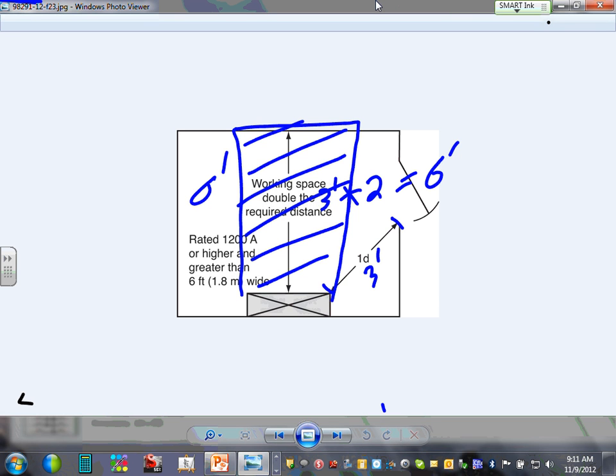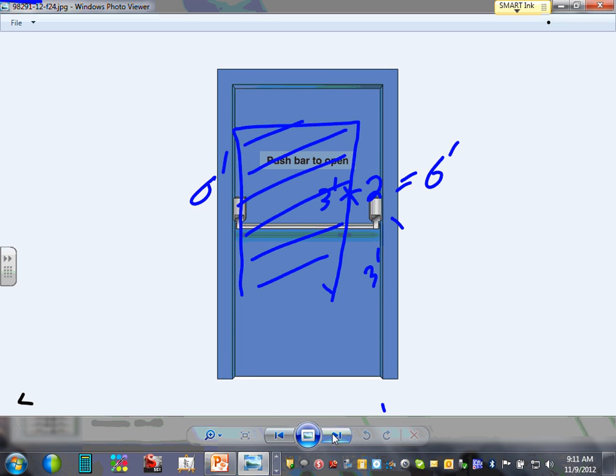Cool? 1200 or more than 6 feet, you need to have 2 entrances. Only 2 exceptions for this. If the switch gear is oriented where the door is straight in front of it, 1 entrance. If you double the distance, if the distance is say 4, you make it 8, double the working distance. Can I have thumbs up, Chad, for the working distance and double the working distance? So that's my electrical room. So that's it, guys, in terms of the clearances.